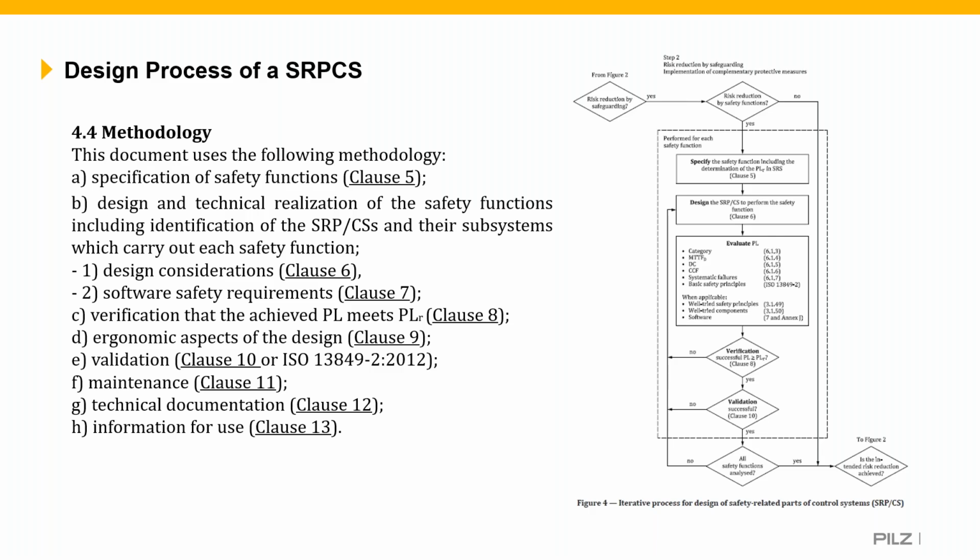Then we go further down through the verification, which is often confused with validation. Verification is the calculation, and validation is the physical testing of the system with fault injections, etc. At any of these points, if you fail, you have to go back up to the top and restart the process. So it is an iterative process for the design, and you have to keep analysing and going around. At any point you deem that you've fallen short, you go back to the top and restart the process.